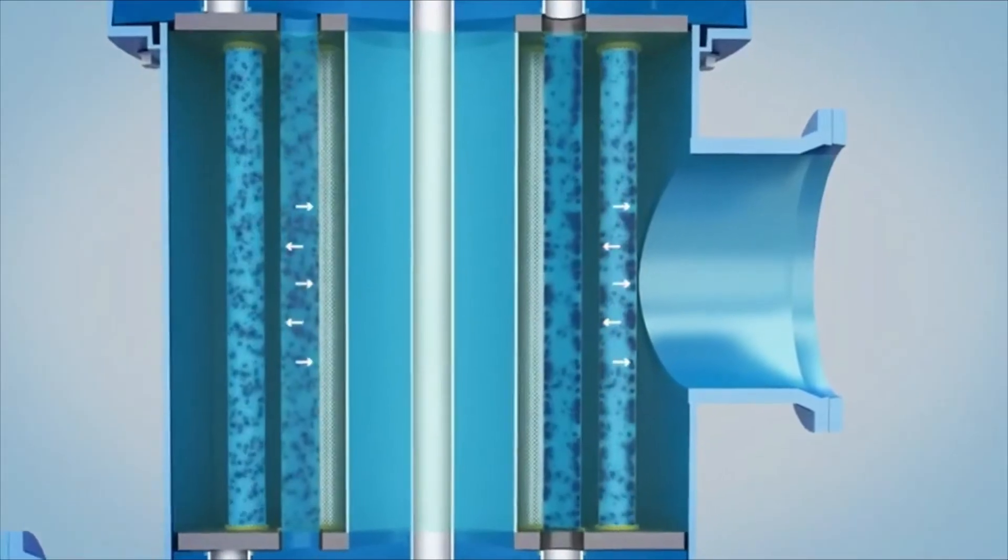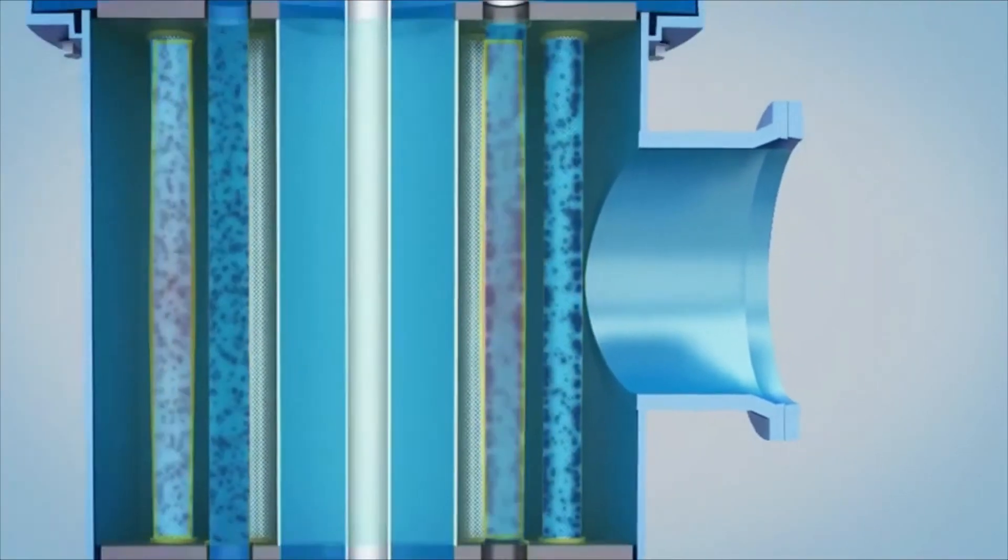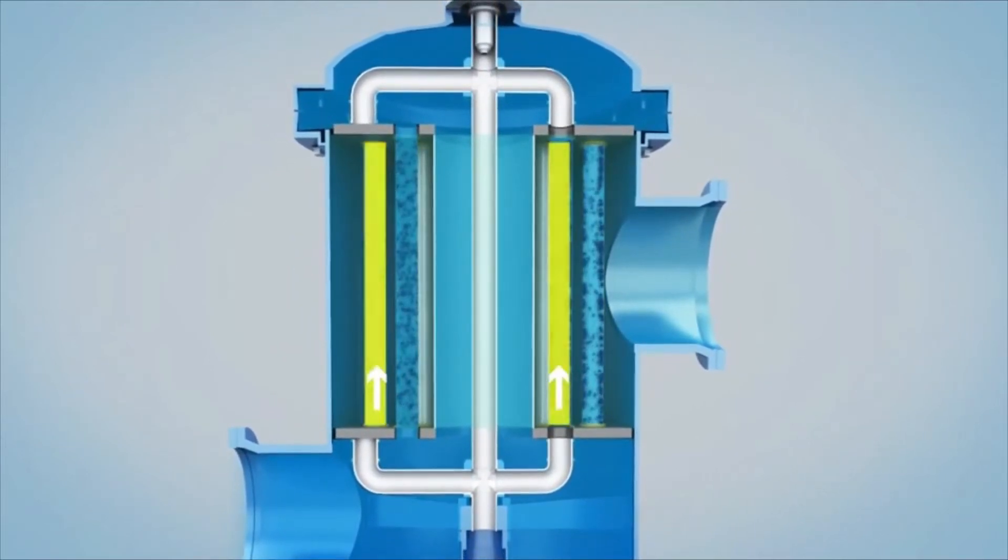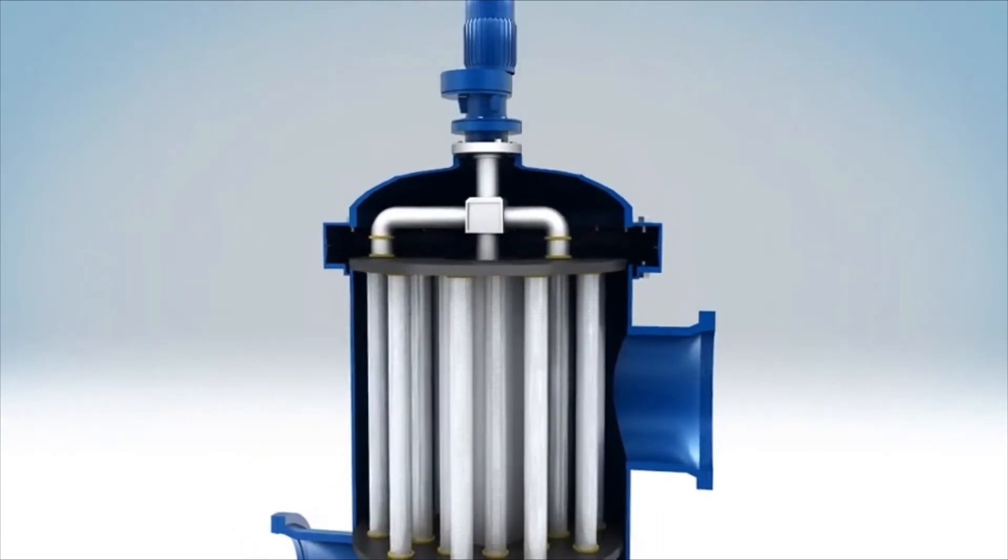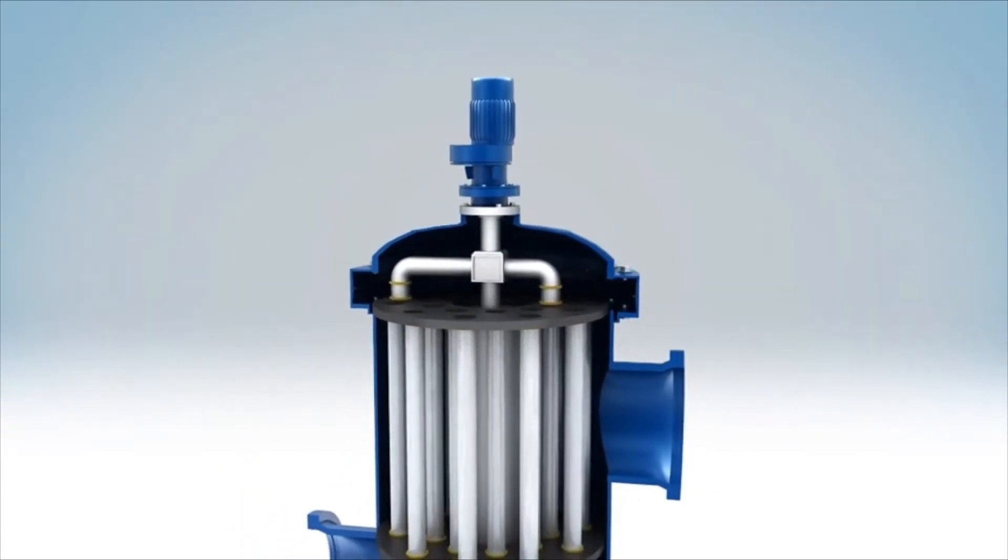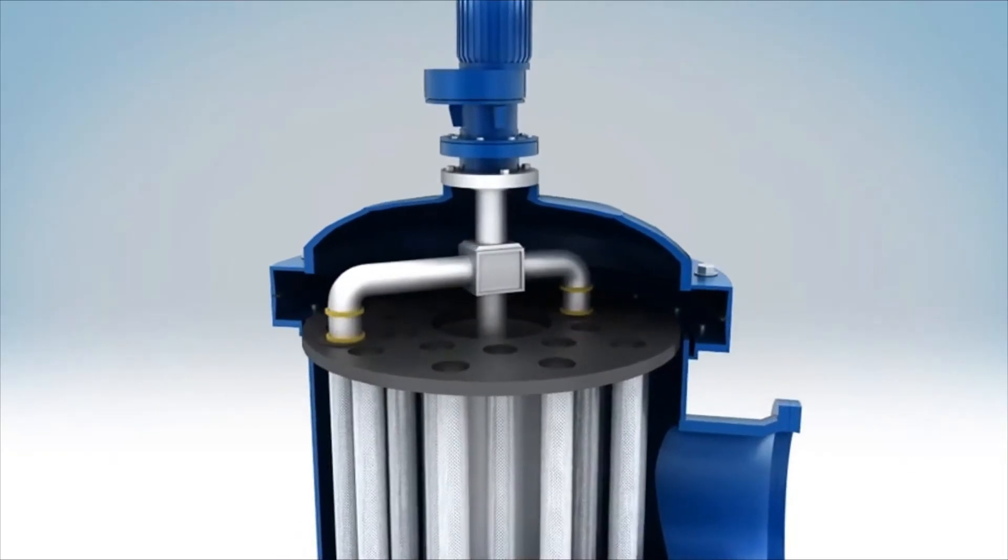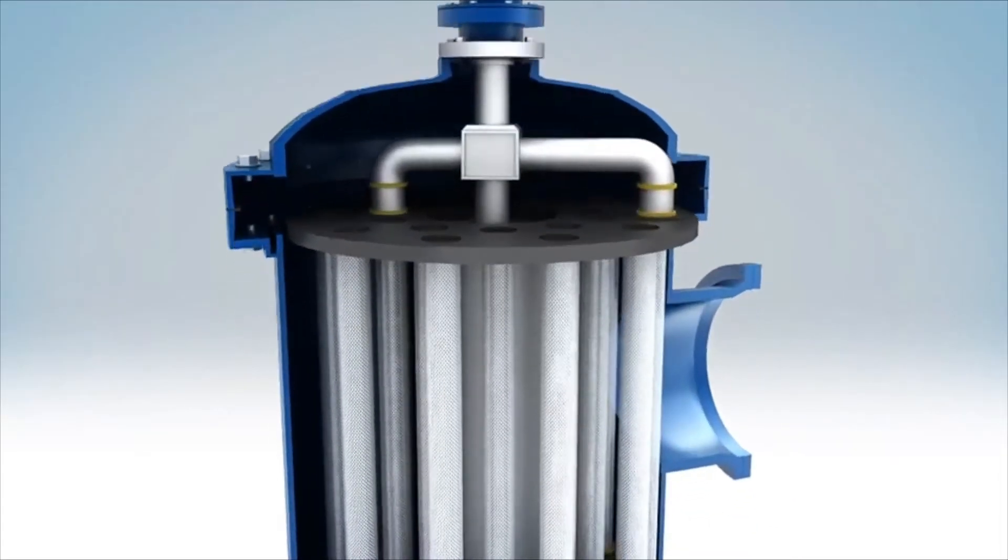When the pressure drop between the internal and external of the filter mesh rises to a set value, the filter operates back flushing process automatically. The filter meshes, which are open at both ends, will be alternately flushed in sequence from above and below. This action doesn't interrupt the normal operation. The flushing arm on the top of the filter rotates by gear motor and covers the upper opening of the filter mesh.